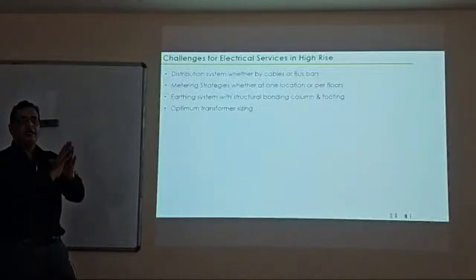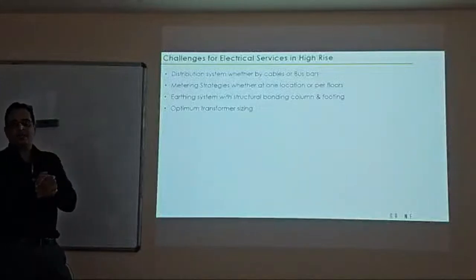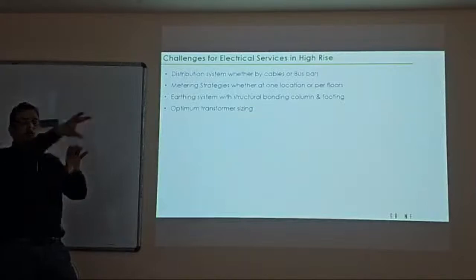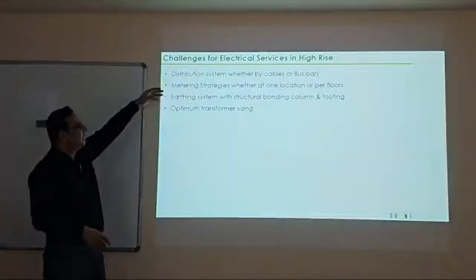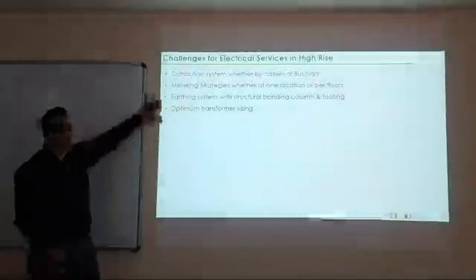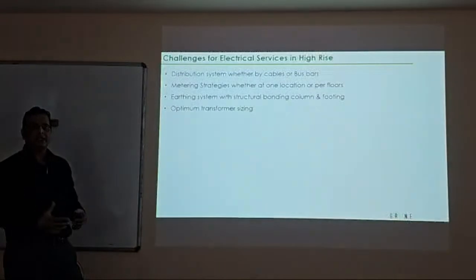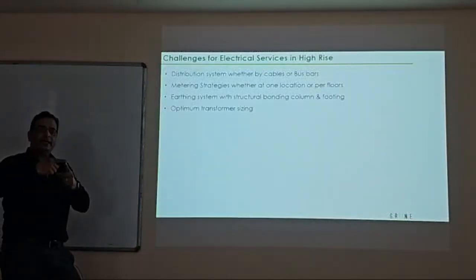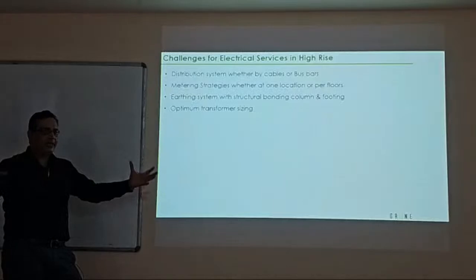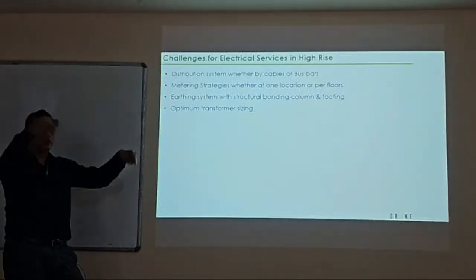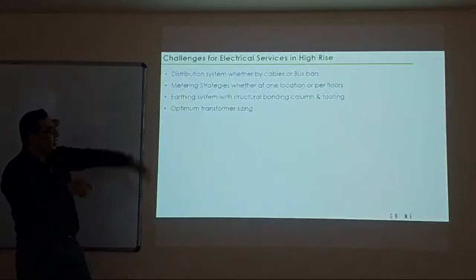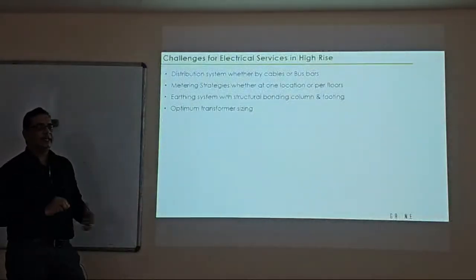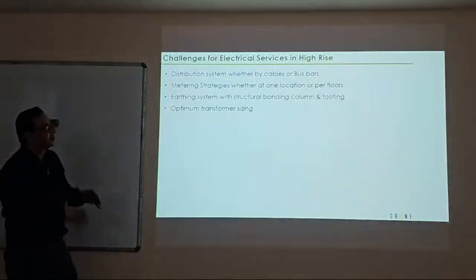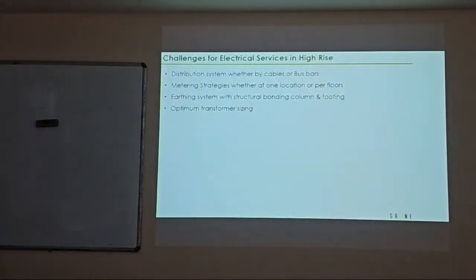So bus bars are designed in such a way that they are sandwiched and insulated, and will not create any short circuit. But you can tap off for 4 floors from one single floor and utilize the design. The earthing system of a building is the most critical design that goes with the rebars. The structural designer will give you an external rebar, and the earthing is connected so that any short circuit that happens within your building, your neutral gets connected and you are able to pull it out of the building without getting electrical shocks. Then sizing the transformer. These are challenges we need to address as we move forward.